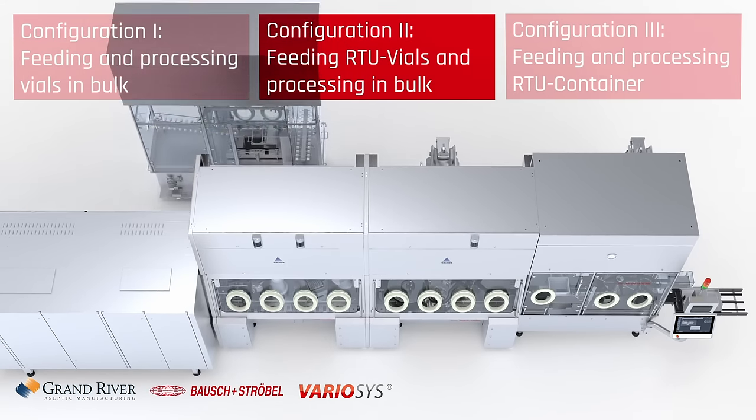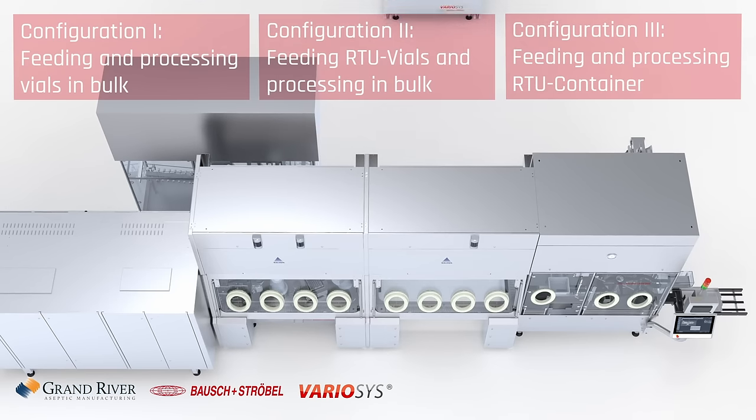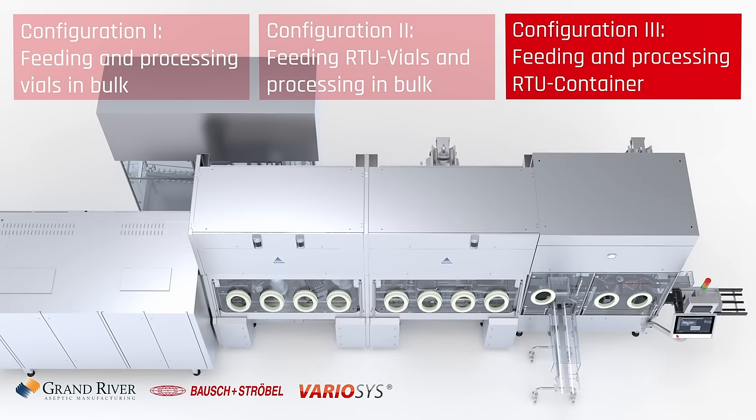So you can have a vial filler, a syringe filler, an aseptic formulation isolator, a bag filler, an IV bag filler — all using one room and one isolator. The VarioSys allows you to have multiple filling technologies in one dedicated fill room. For example, if you wanted a vial filler, a syringe filler, and a bag filler, typically you would need three isolators in three separate fill rooms. With the VarioSys, you can have one fill room with all three different filling technologies.